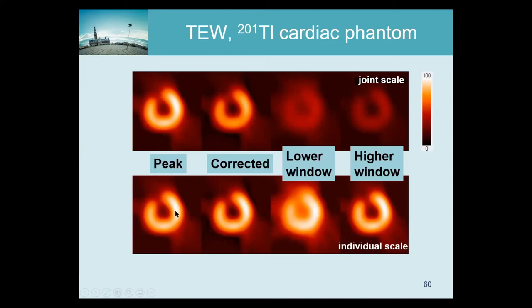And then you can see that after correction, for example, this is the wall of the left ventricle imaged with poor resolution because this is an old slide and thallium is not an ideal isotope. But we know that at the time that this image is taken the blood is cold, so there should be no activity inside the heart, and you see that there is activity here but now it's corrected to zero here, so that's good. We see that in that lower energy window the resolution is much worse than in that higher energy window. That is logical because what we see, scattered photons there, so that is fine. So this should be a reasonable estimate of the scatter in here. And then we see that in that higher energy window, actually the resolution is just as good as in the primary window, so that thallium has these two energy peaks. So it probably has seen some scatter from the higher energy window, but it actually saw more trues than scatters, which is why it has excellent resolution. So probably we don't need that window here for thallium.